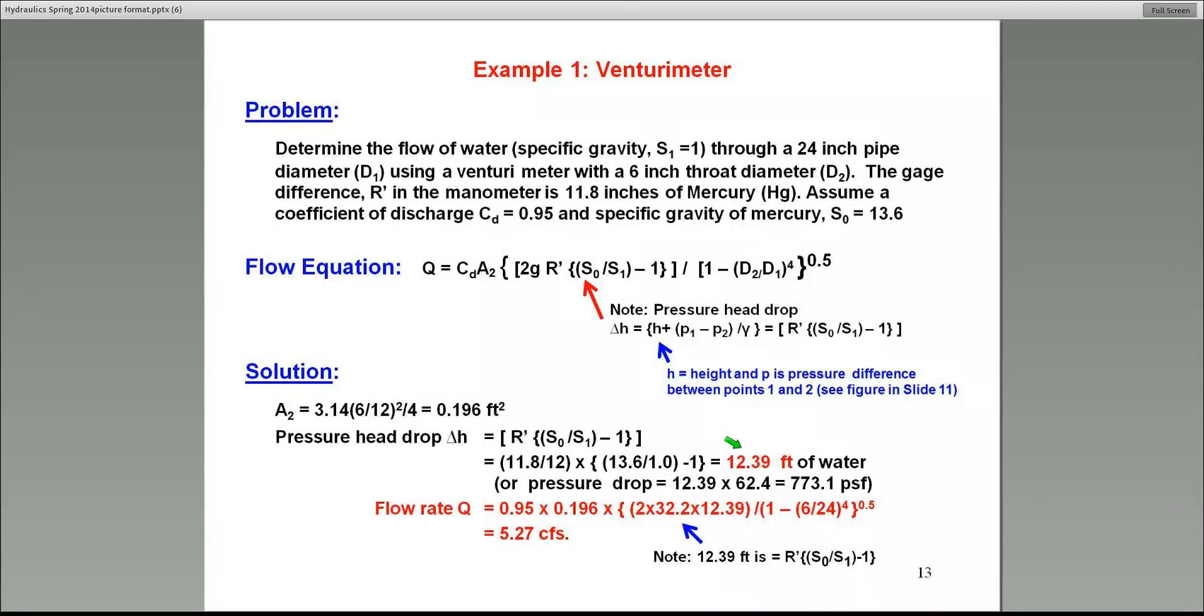Now, here's the equation that I was looking at as an example. In this case, the CD, the coefficient of discharge, is given as 0.95. And therefore, I'm going to use that essentially in the equation here. Also note that the pressure drop that we calculated is about 12.39 feet of water. And therefore, it's substituted in this equation to calculate Q. So the final product is Q, which is CD times the pressure drop. And of course, multiplied by this quantity called, or divided by 1 minus D2 over D1 to the power of 4. So you all can do these calculations. I've just shown it to you in this example. The final flow rate through the pipe is 5.27 CFS.